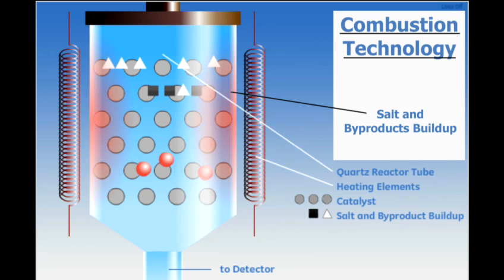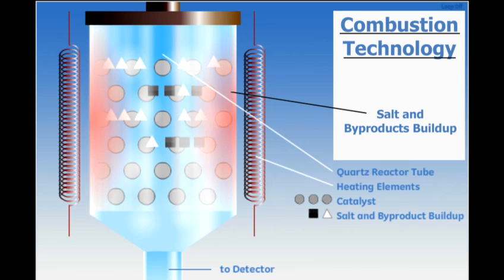Combustion analyzers have very aggressive oxidation, but they don't handle dissolved solids like salt very well. Persulfate analyzers offer much cleaner oxidation, but they tend to have low recoveries for difficult samples.